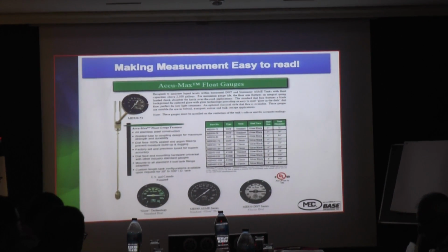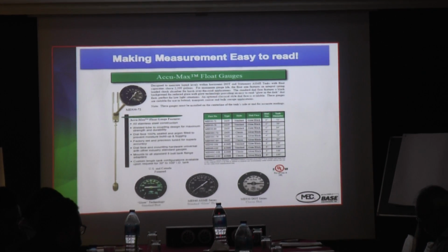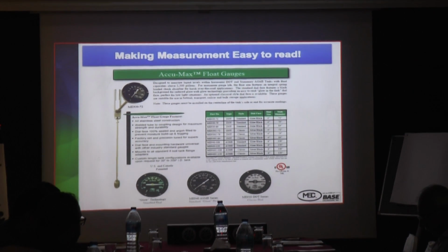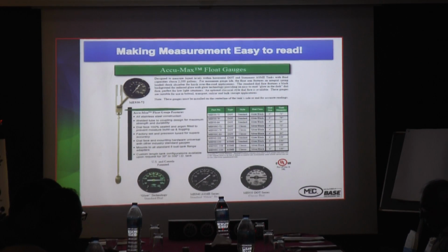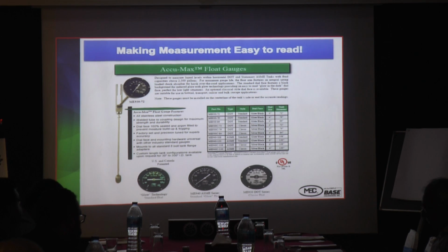The other thing is that we also get feedback that most of the gauges in the market, during rainy days or hot days, become very foggy. You can't read it from where you stand because there's moisture inside the dial face. So what we do here is we fill the dial face with argon and we seal it so that no other gas or humidity vapor gets into the dial face to create mist and fogginess on the dial.